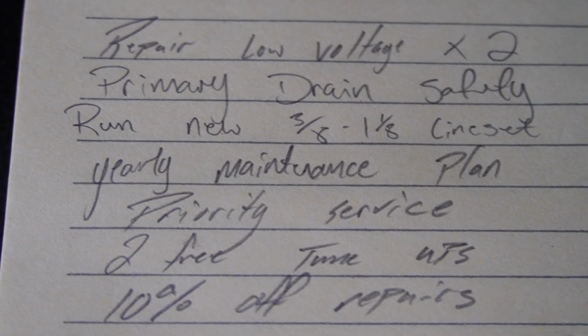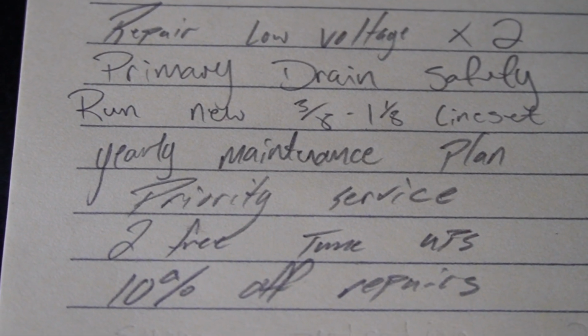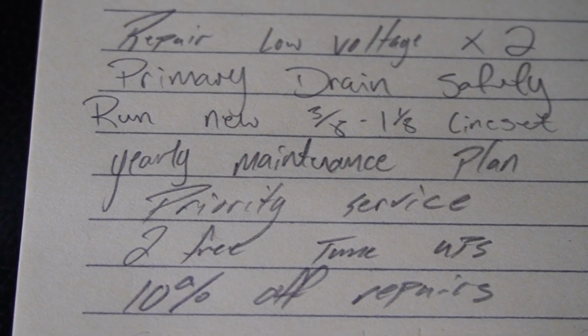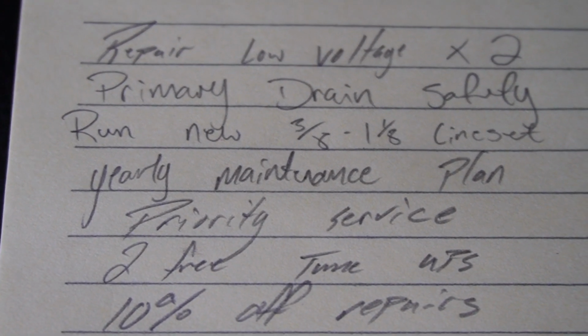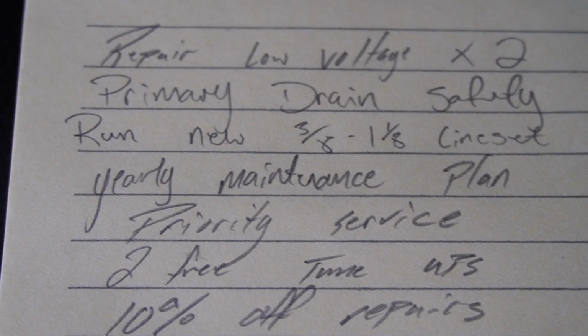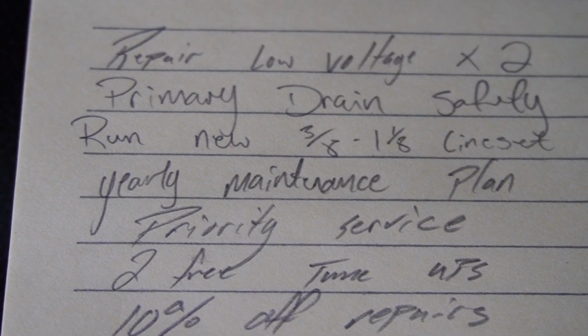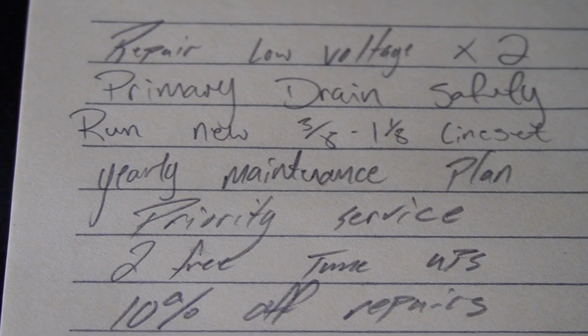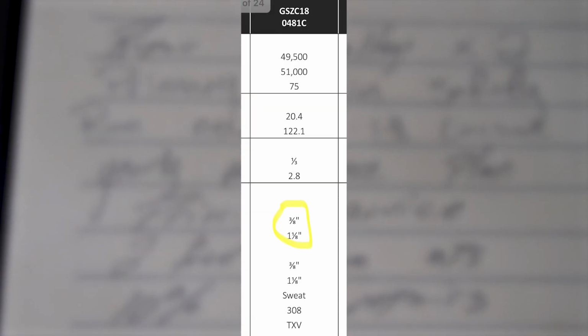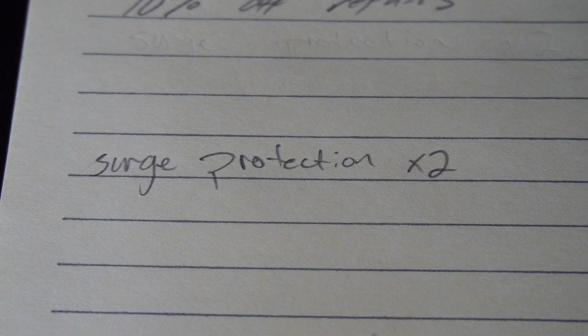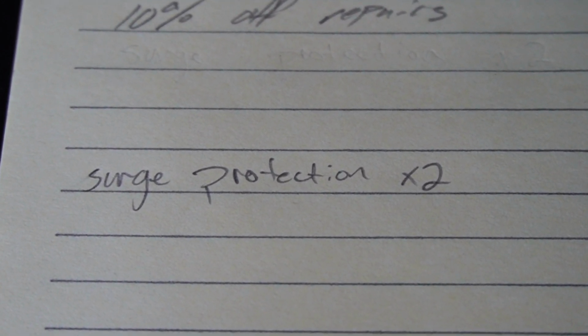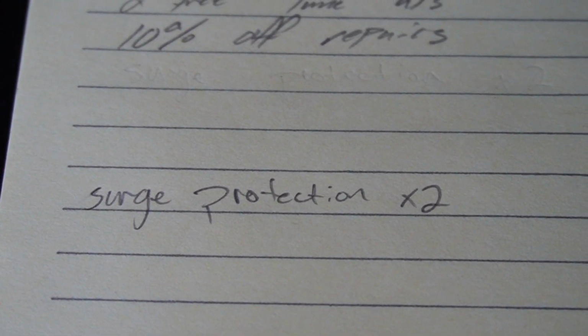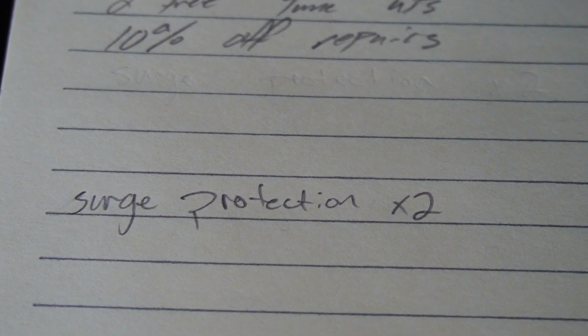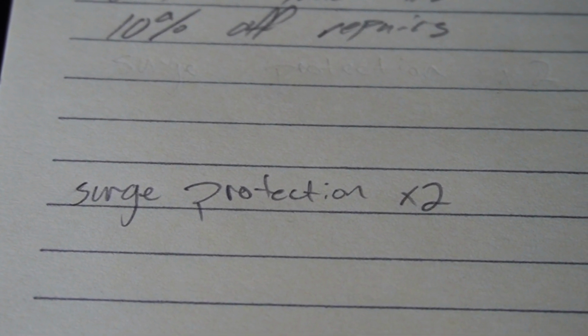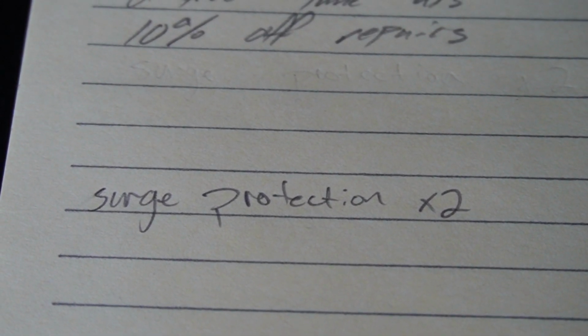Then we've got primary drain safety, taken to the air handler. That unit calls for 1⅛ suction line, 3/8 liquid. So that right there is something that should be done to get this unit running properly and living its best life. I'll put the screenshot in here we found on Goodman MFG for the unit itself. Also, surge protection for this nice fancy piece of equipment would definitely help prevent any major repairs needed due to surges, lightning, brownouts, and that.